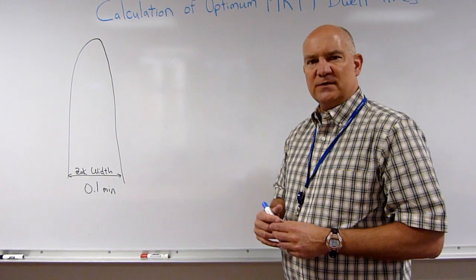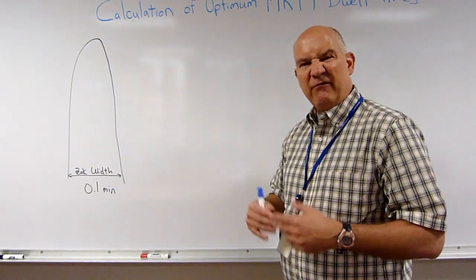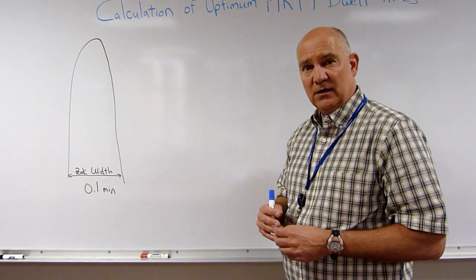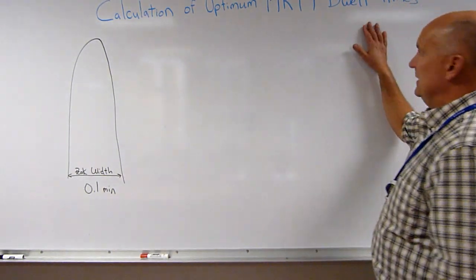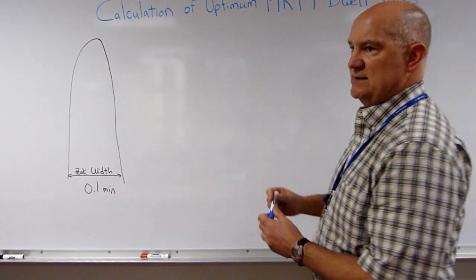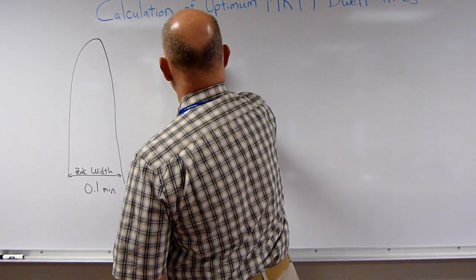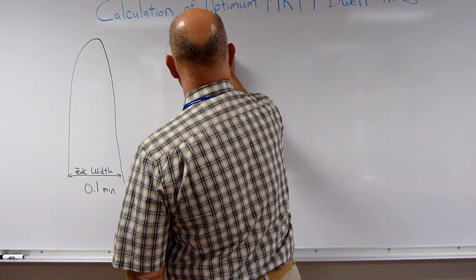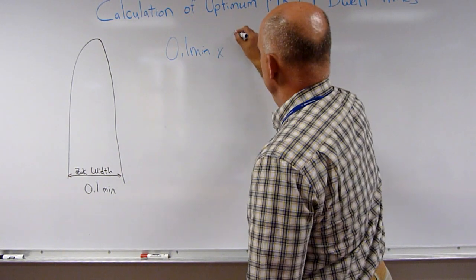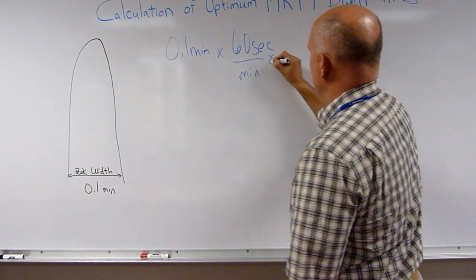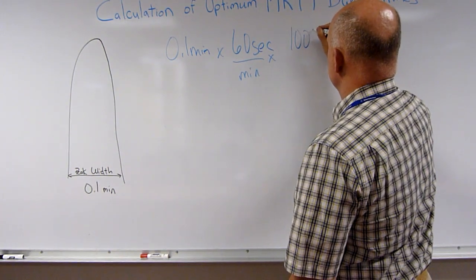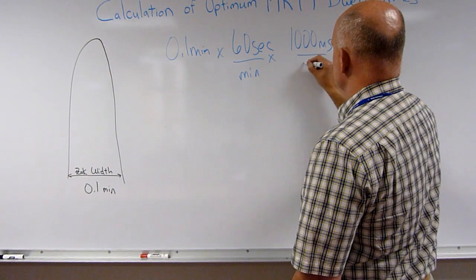Most of our chromatograms on the x-axis have minutes as the axis. If you do, your number will be expressed in minutes. Dwell times are typically expressed in milliseconds. So we must first convert from minutes to milliseconds. So we have 0.1 minutes times 60 seconds per minute times 1000 milliseconds per second.